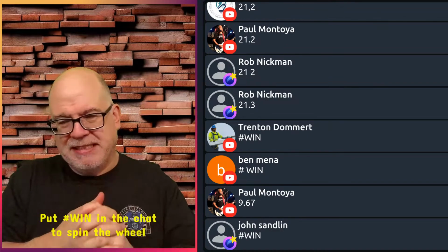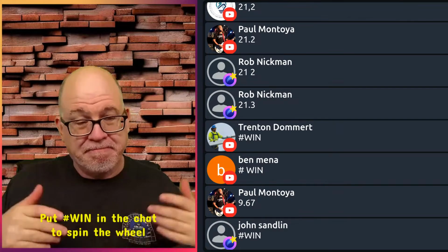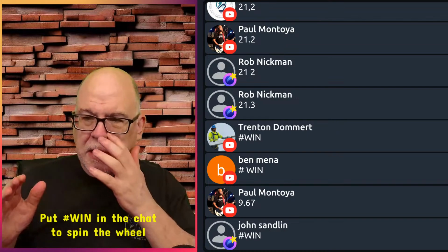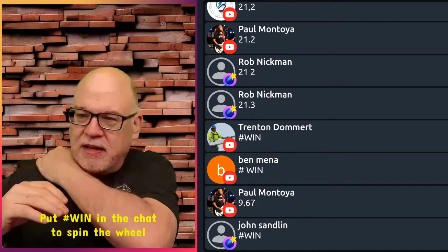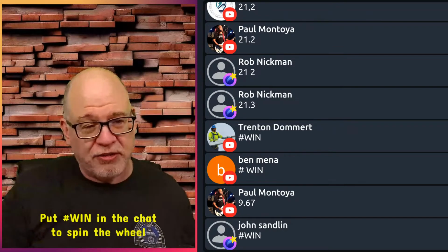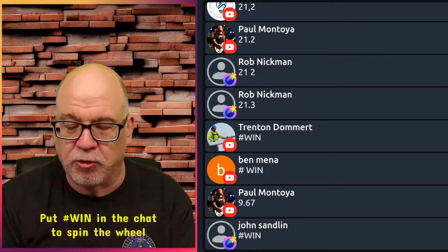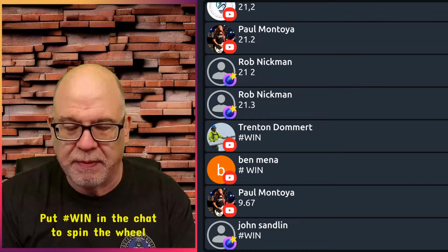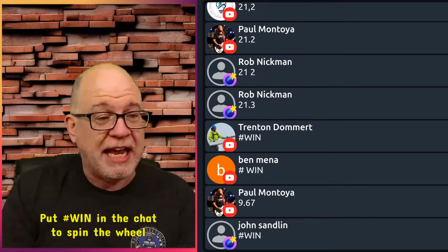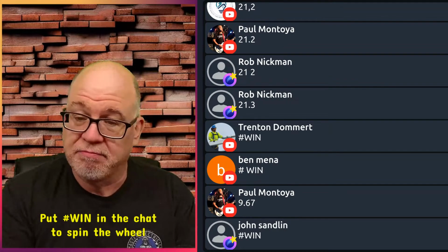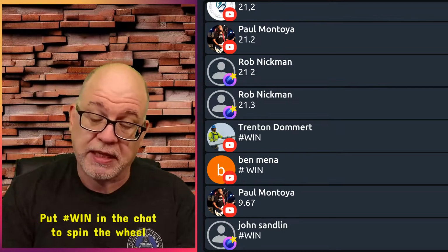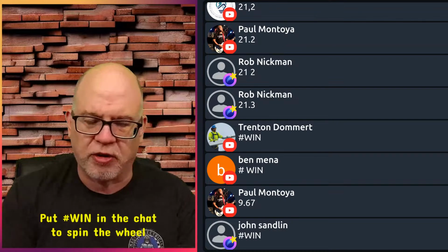So, yeah, at the end of the day, that's how I do it. Now, somebody might say, well, Paul, say it's a branch circuit. Is this exceeding the 3% on a branch circuit? Well, to do that, I'm just going to take that 240 times 3%. And that's 7.2. So the answer to that is yes, it's exceeding the 3%. Right now, is it exceeding the overall, let's say 5%? Okay, because we don't know, we assume this is a branch circuit, but is it exceeding?